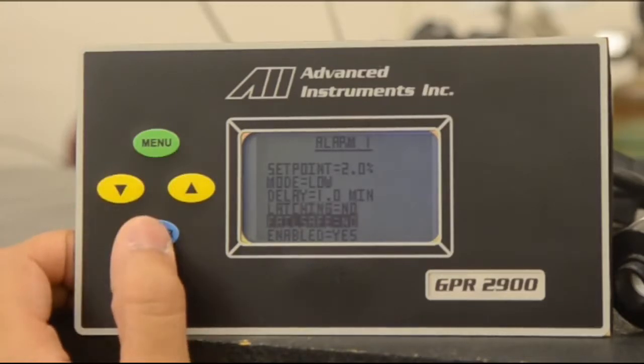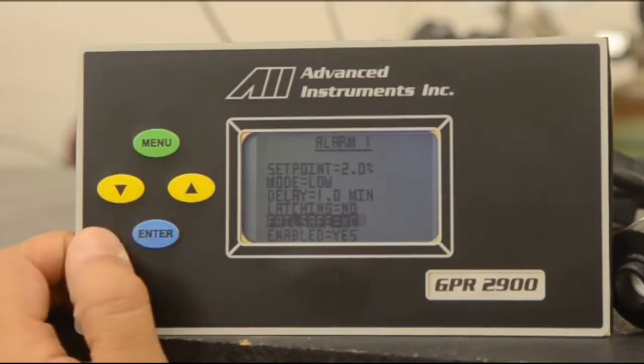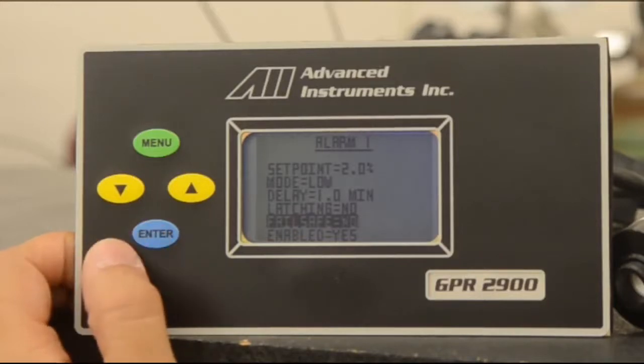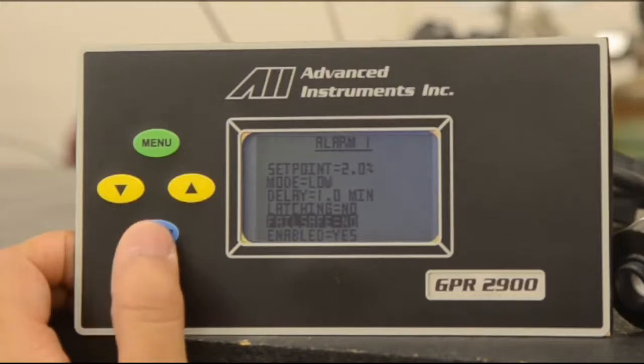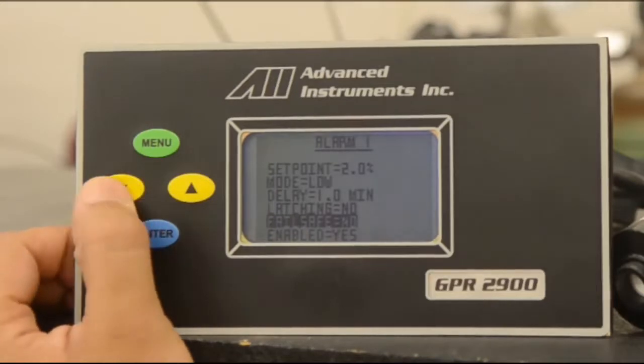You also have the fail-safe option. Enter for yes, enter for no. The fail-safe option allows the relay to be energized on non-alarmed states and de-energized in alarmed states. This is used if you would like to have a power failure option, or if your analyzer loses power, to have a backup to seal any type of connection you have to the alarm.